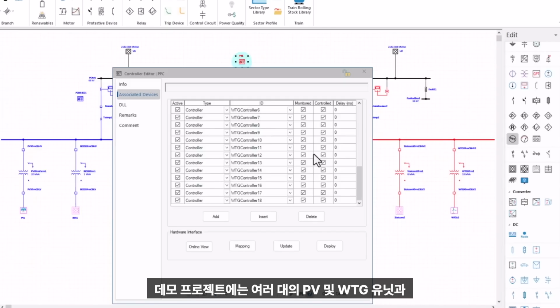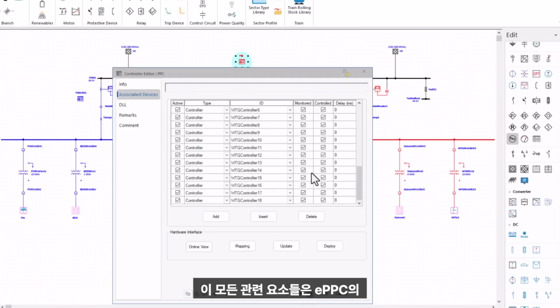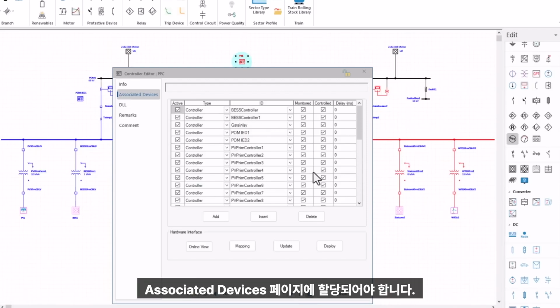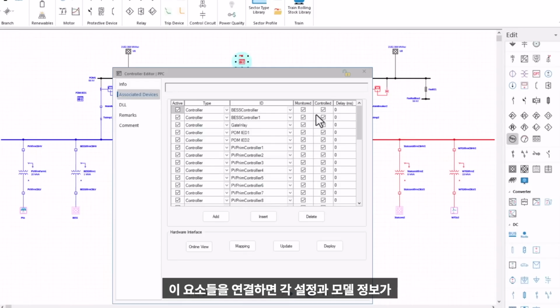In our demonstration project, we have several PV units and WTG units along with their corresponding PV and WTG controllers, 2 battery energy storage systems, 2 STATCOMs, 2 POM meters, and 1 gateway controller. All of these relevant elements should be assigned on the Associated Devices page of the ePPC. By associating these elements, their settings and model information are automatically transferred into the ePPC environment without requiring manual reentry. This is one of the major advantages of ETAP's model-driven structure, since it improves both the efficiency and ease of use while reducing the chance of configuration errors.